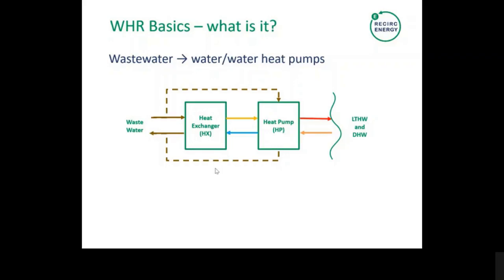What we're talking about are essentially water-to-water heat pumps, but rather than using rivers, groundwater, etc. as the heat source, we're using wastewater, and obviously that requires a certain amount of unique pre-treatment before it can be put into a heat exchanger, or in some cases directly into a heat pump evaporator. So we're going to go through some of the technology, some of the configurations, some of the potential applications of the technology.